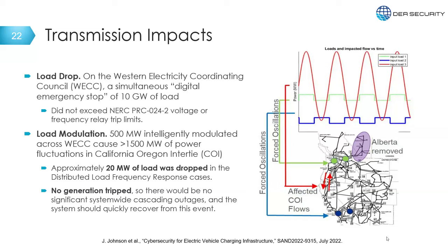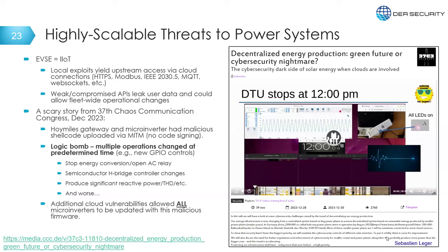So these inter-area oscillations, if you swing the loads against one another, with only 500 megawatts you start to get a 3x multiplier on the California-Oregon intertie, and this can cause issues. What we found is you get a little bit of load drop based on protection issues, but no generation was tripped.